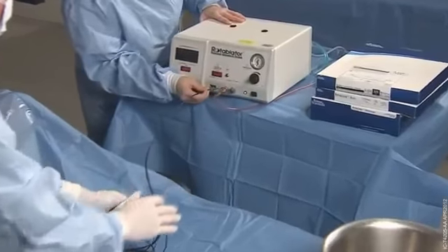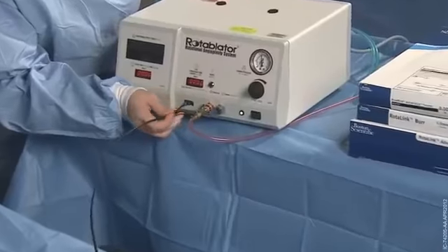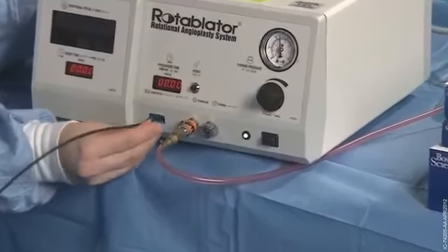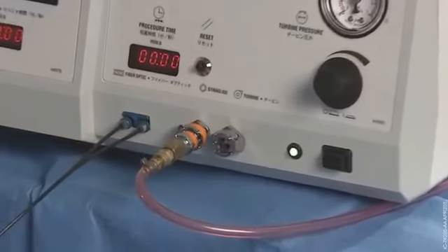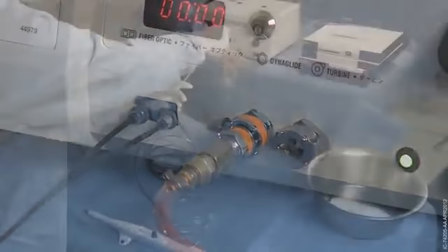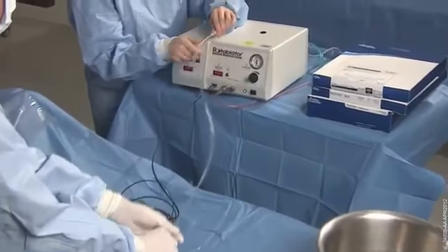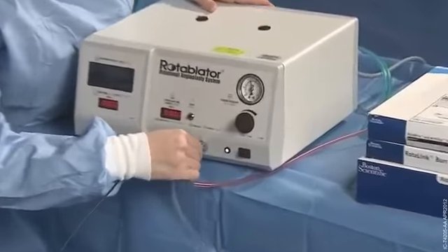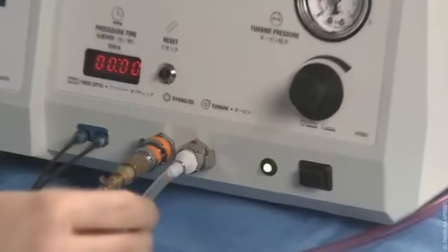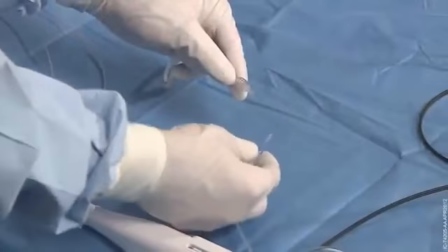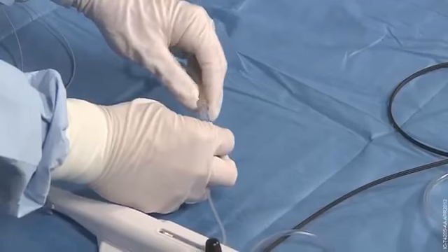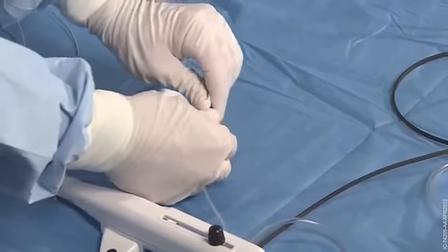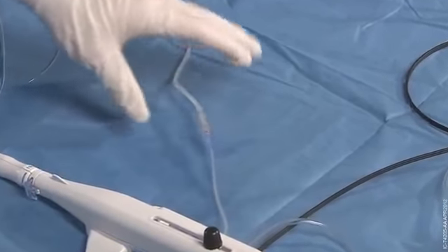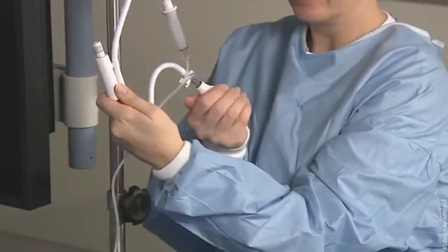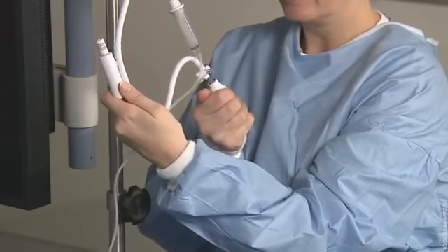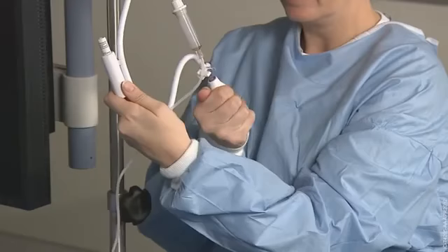First, attach the advancer connections to the console. The black fiber optic cable connects to the front panel of the console. The compressed gas connector connects directly to the turbine port on the front of the console as well. Attach the saline infusion port of the advancer to the IV tubing of the irrigation source. With the pressure cuff in place around the saline bag, inflate to approximately 200 millimeters mercury.